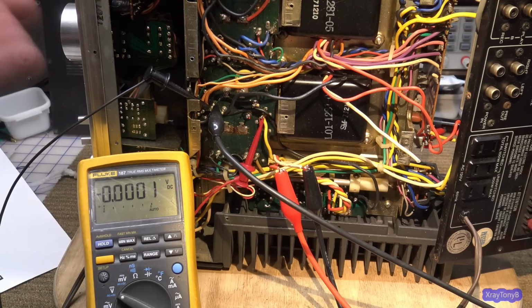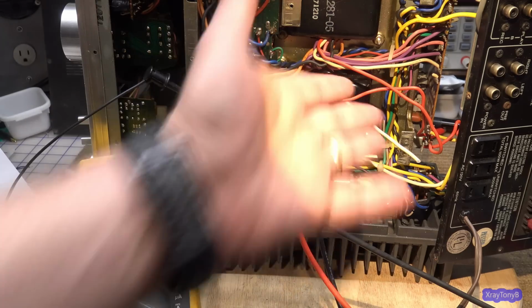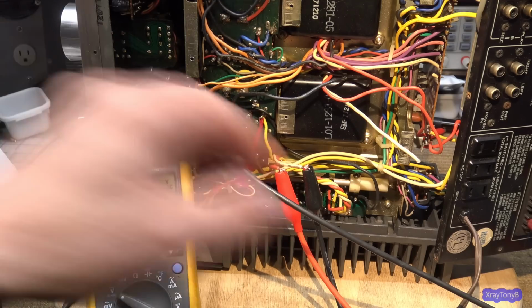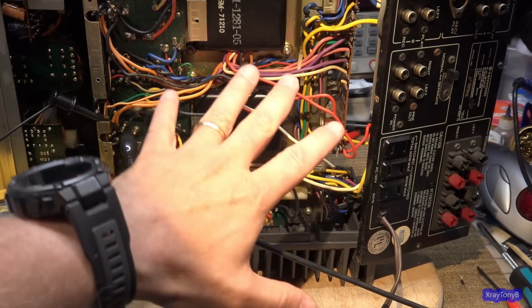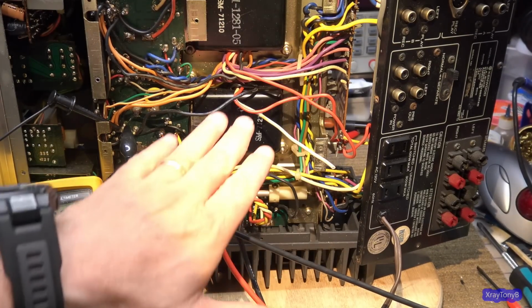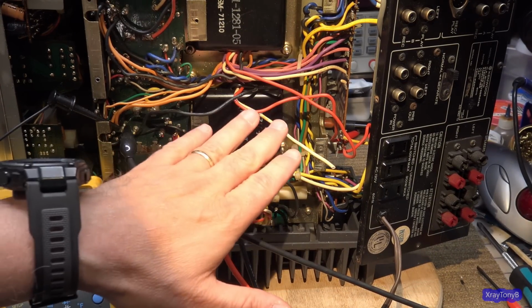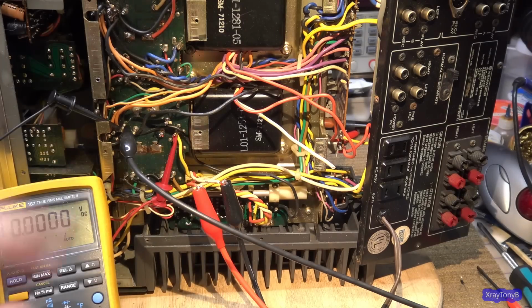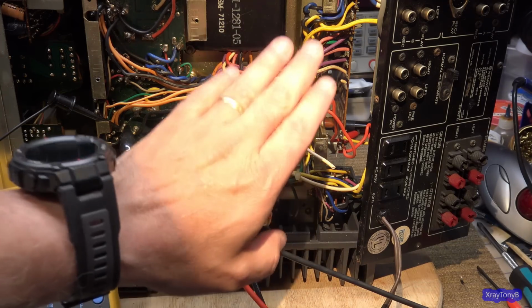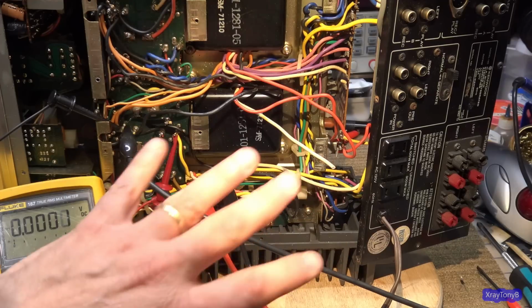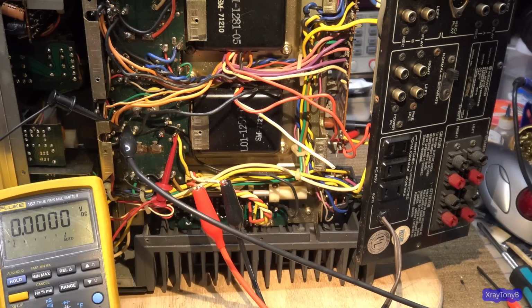Now, chicken or the egg? Did that power module take out the transformer? How could that have happened? I mean, the primary of the transformer is open, and I've verified that, no doubt. If the primary of the transformer is open, that means it would have had to have drawn enough excessive current to take out that winding.